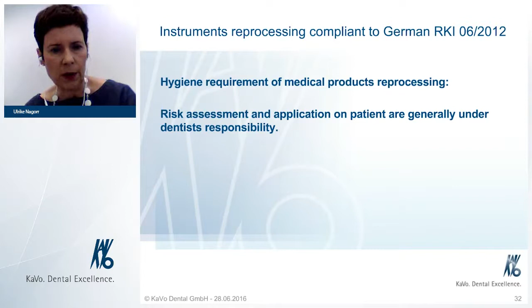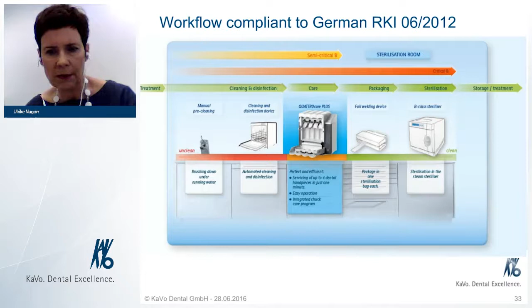The workflow, according to the German Robert Koch Institute's regulation, looks like this. In the hygiene room, you have a so-called unclean area, marked here in red, and on the right side you see the clean area. Here the instruments have to be handled in an appropriate way, either as semi-critical B or critical B, beginning with a manual pre-cleaning, just brushing, washing under fluent cold water, then cleaning and disinfection, ideally in a thermal disinfector, a lubrication process, then a packaging process if it's a critical B, or just autoclaving if it's a semi-critical B, in a steam autoclave, Class B autoclave.